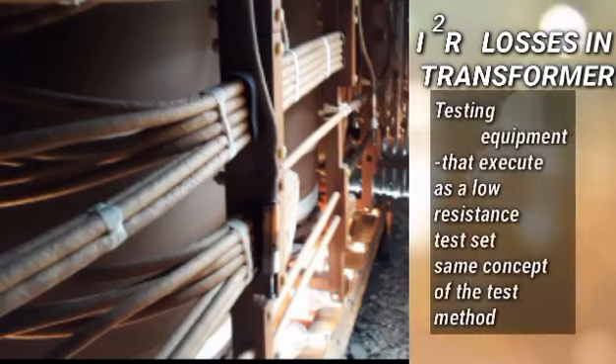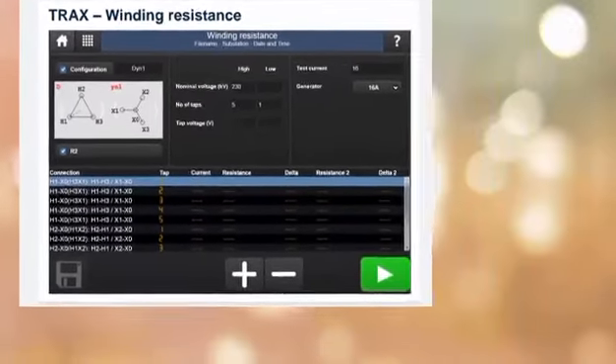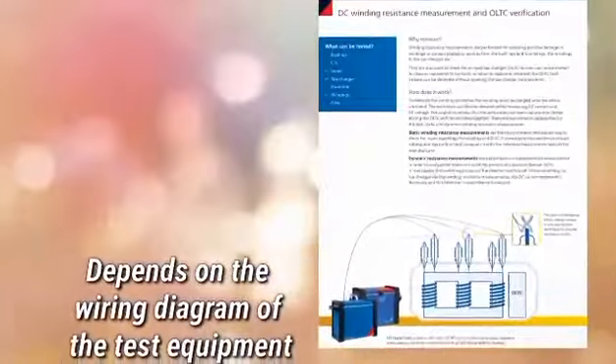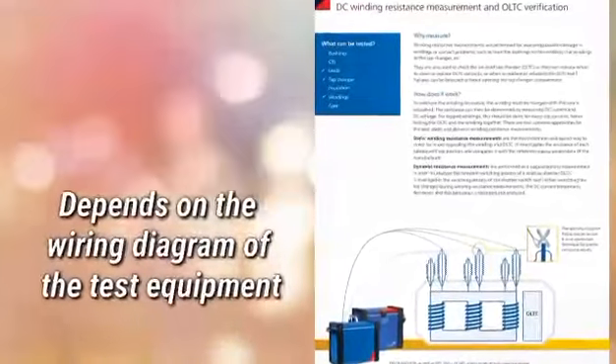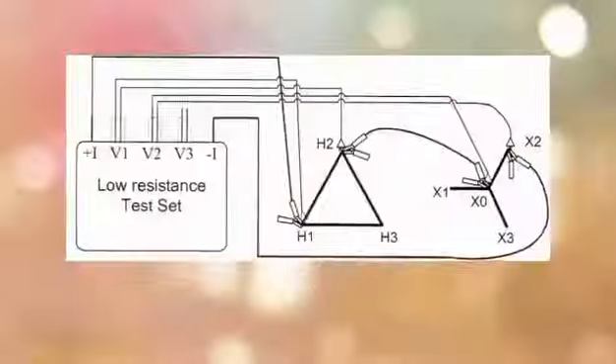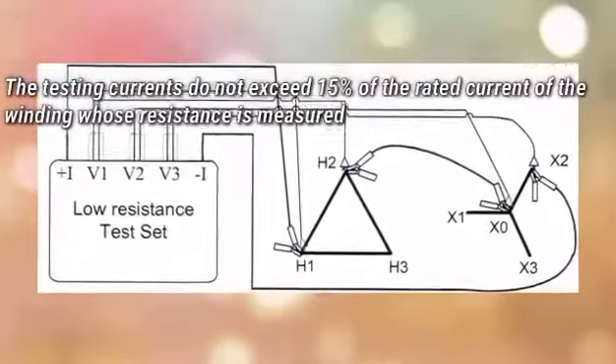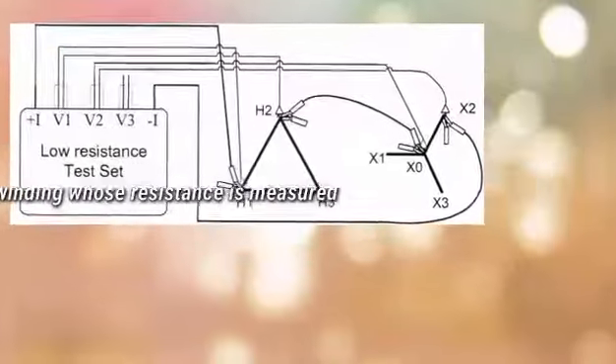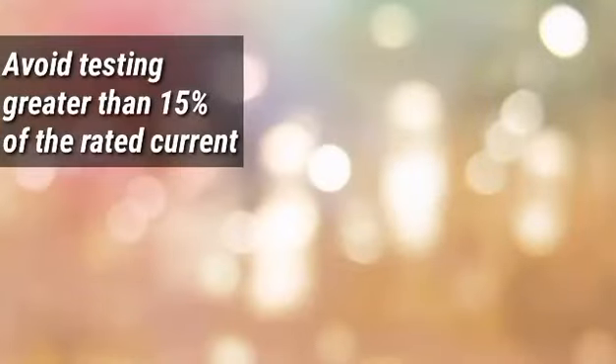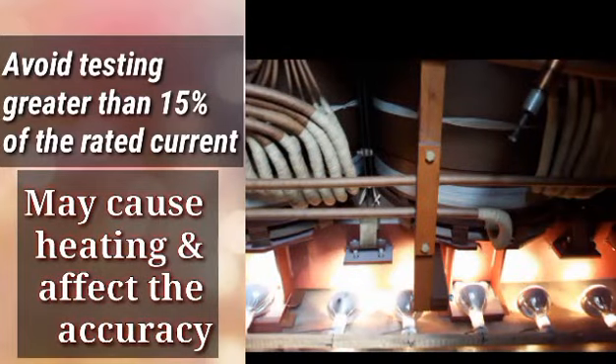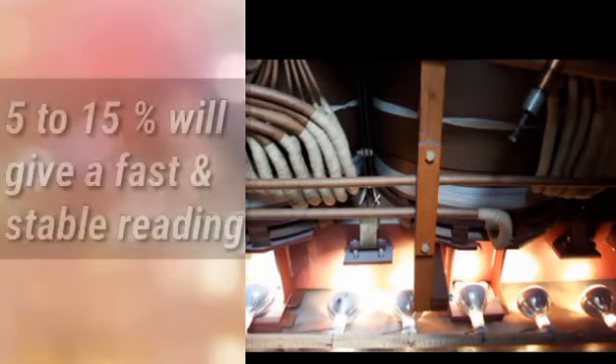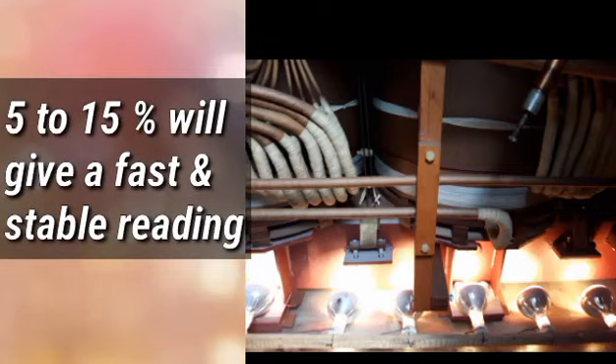Although there is a lot of testing equipment nowadays that will serve as a low resistance test set, the same concept of test method is employed. The method of connections depends on the wiring diagram of each test instrument. One of these is the voltmeter-ammeter method, used for measuring the winding resistance of each terminal and/or each tap point. The testing currents do not exceed 15% of the rated current of the winding whose resistance is measured. Avoid testing at greater than 15% of rated current since this may cause heating which will affect the accuracy. Typical test currents are 1 to 15%, and using 5 to 15% will give fast and stable readings.